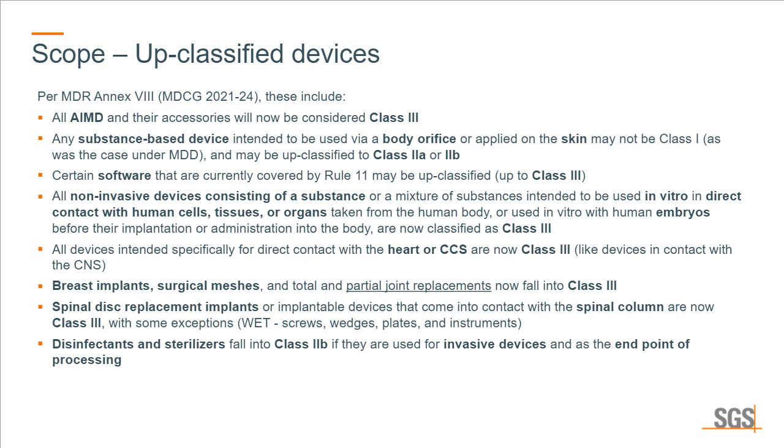All active implantable devices and their accessories are considered class 3. Substance-based devices intended to be used via the body orifice or applied on the skin may not be class 1 as under MDD and may now be up-classified to class 2A or 2B. Certain software that are currently covered by Rule 11 may be up-classified even up to class 3.